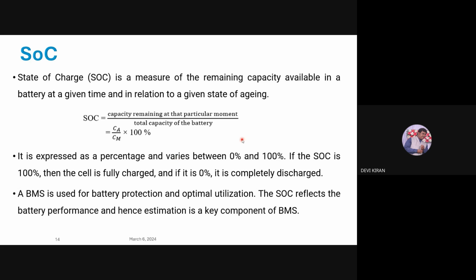You generally denominate the state of the battery from 0 to 100%. But even if it is shown as completely discharged to 0%, that doesn't mean no energy is left in it; there will be some energy remaining. The industrial 0 to 100% barrier ensures at least 20% remains inside, though it's dangerous to operate in that zone. So you'll typically have 10 to 20% spare energy inside, because if the battery completely drains and you charge it instantaneously, it will overheat and enter an uncontrollable zone where it can destroy itself.